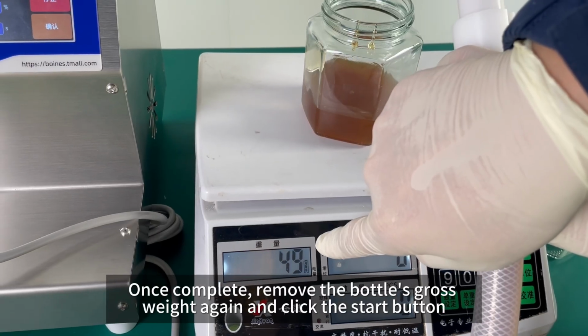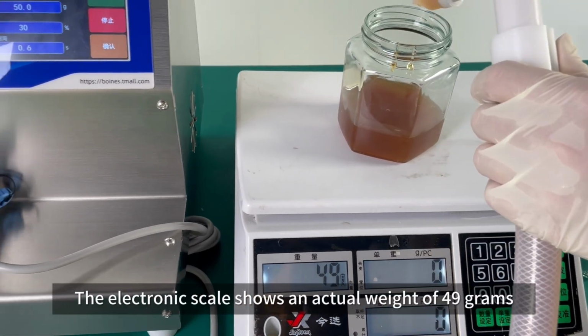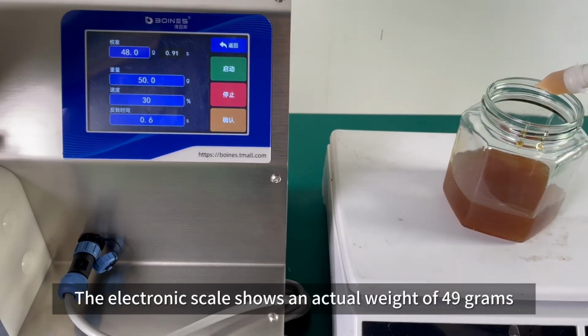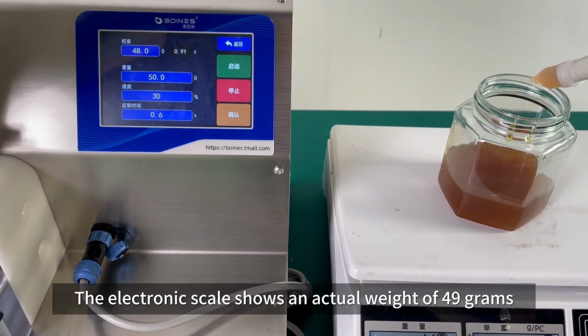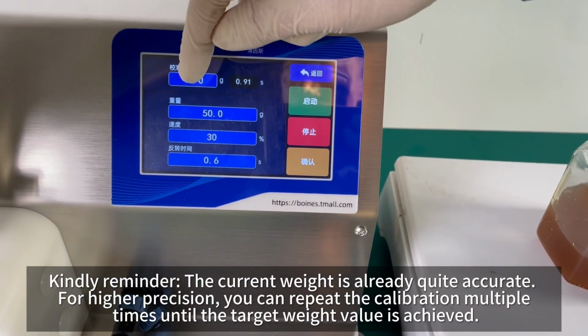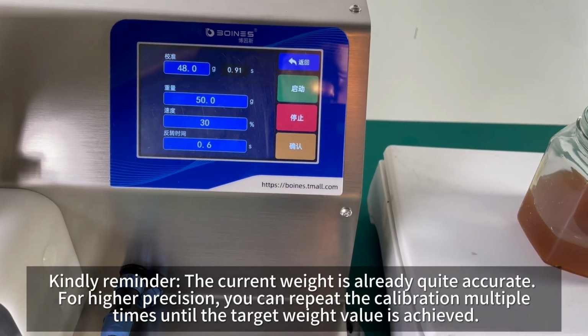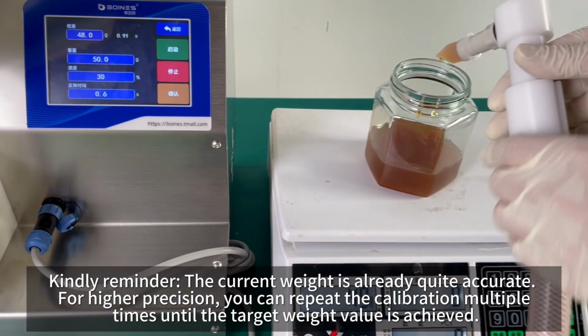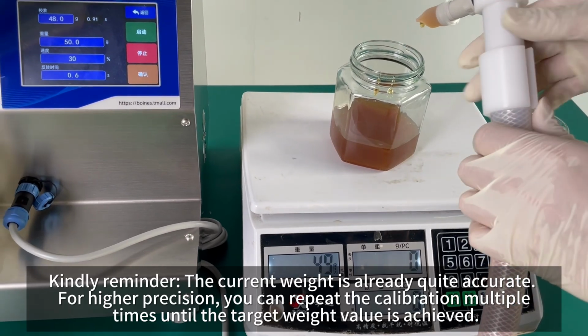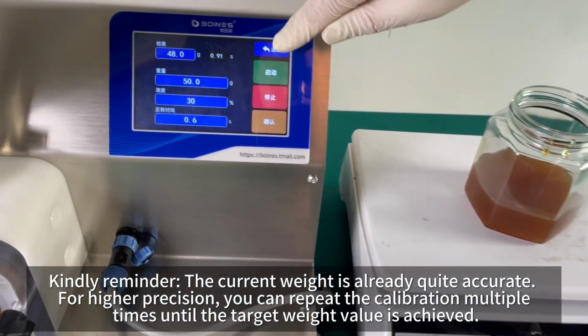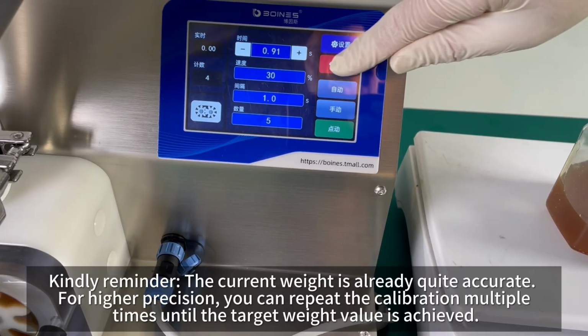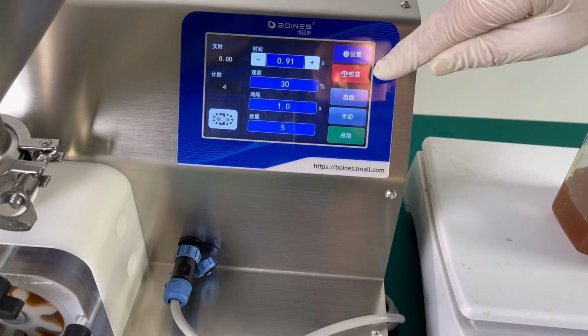Wait again and click the Start button. The electronic scale shows an actual weight of 49 grams. Kindly reminder, the current weight is already quite accurate. For higher precision, you can repeat the calibration multiple times until the target weight value is achieved.